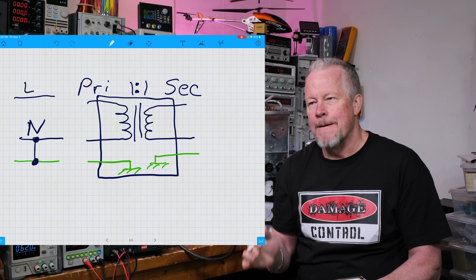But let me explain something here. This ground, these chassis connections—all metal things are going to be grounded to chassis, same connection, the same green wire. So the 3 prongs, that ground connection, the first thing it does is go right to chassis. We want all the chassis connected together so they're all the same potential—we don't want to get shocked when we touch one chassis and then grab another. All same potential, so we always want that, and we want that in our isolation transformer too. So the 3 wires coming in, we want it hitting this chassis.